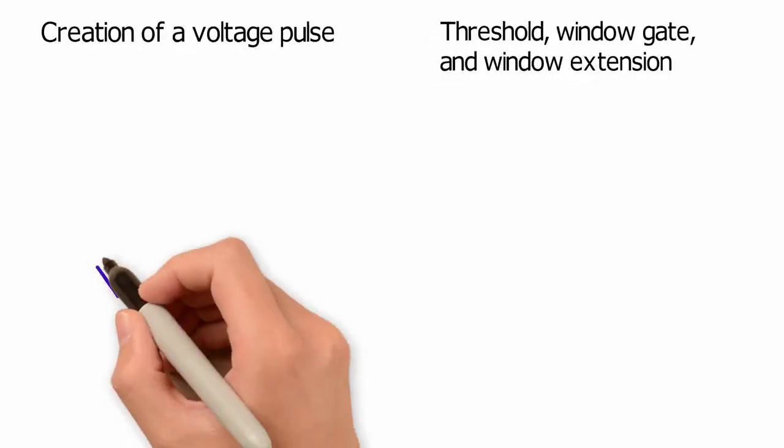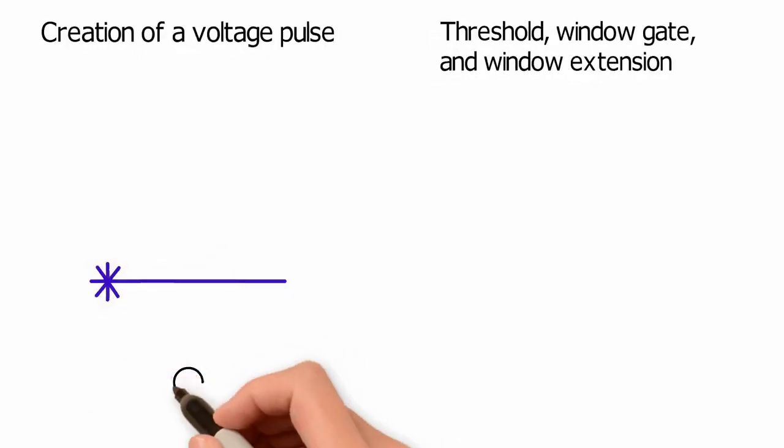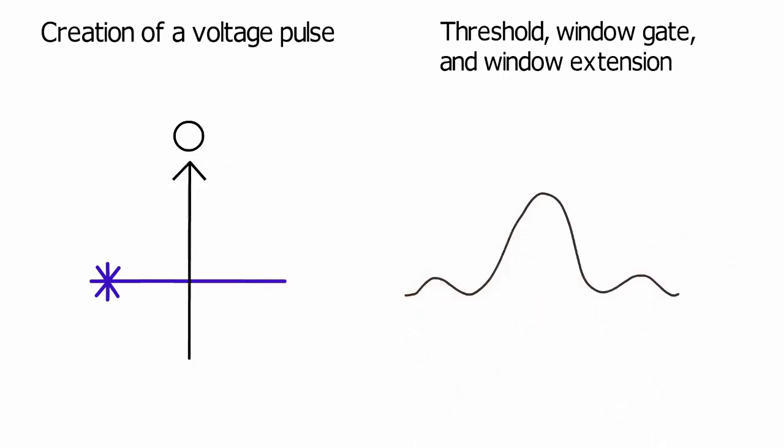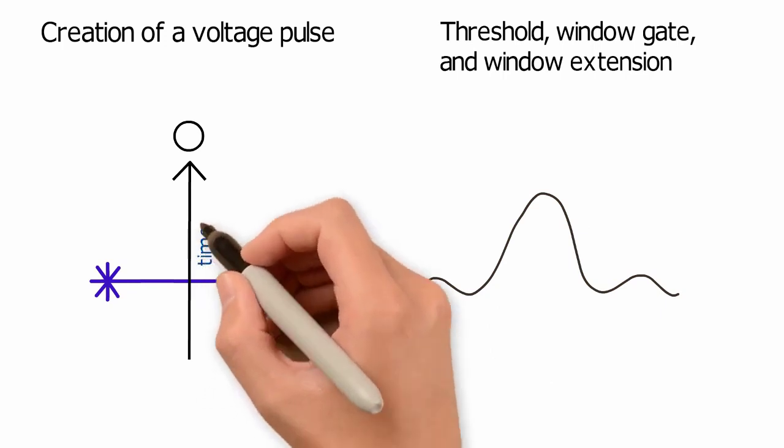The creation of a voltage pulse starts in the flow cell, at the point where the laser intercepts the cell or particle. As this particle passes through the laser, a signal is created. This signal over time is described as a voltage pulse.